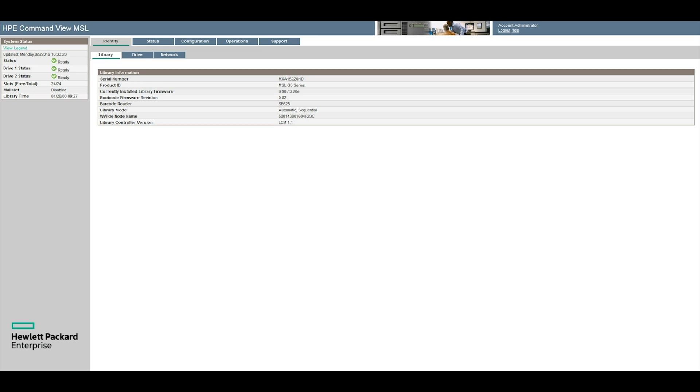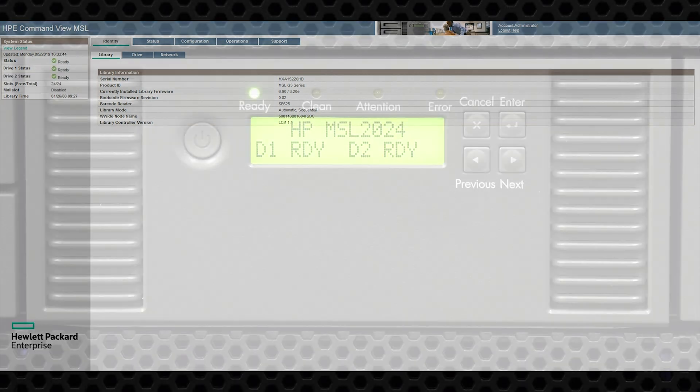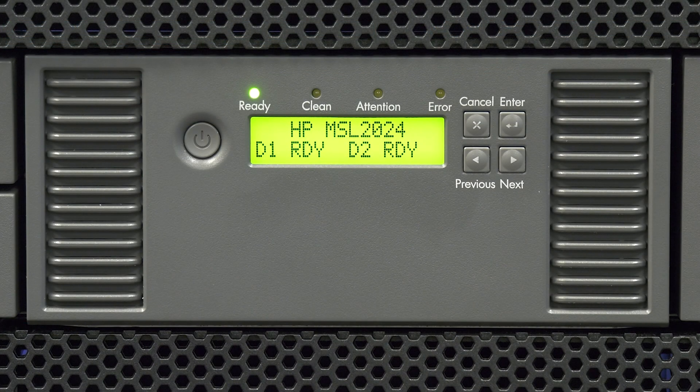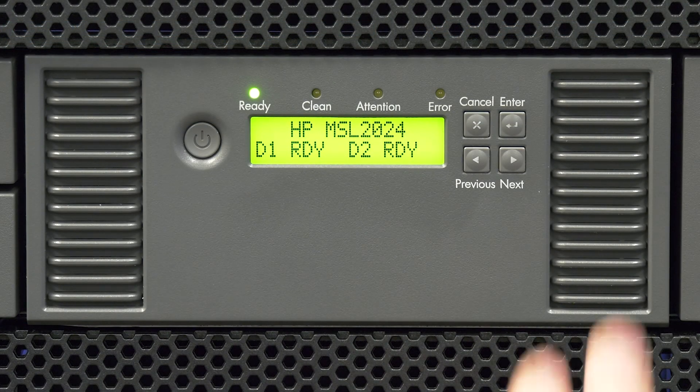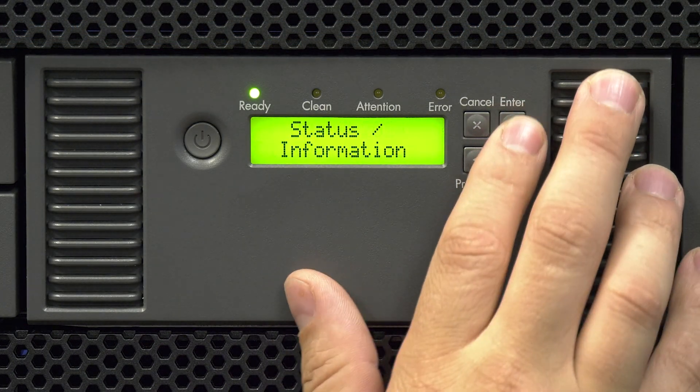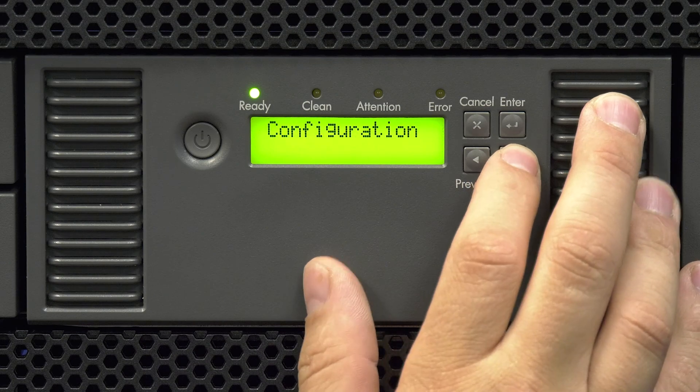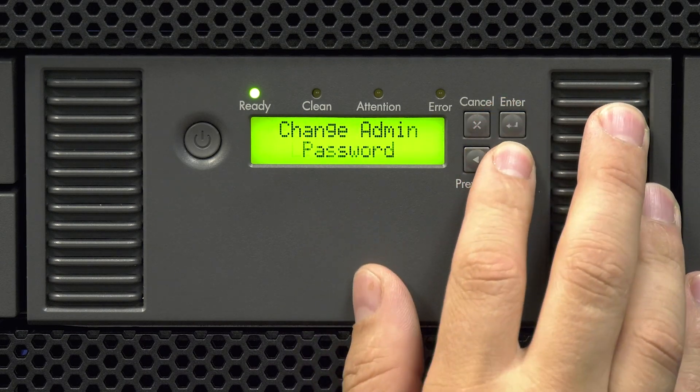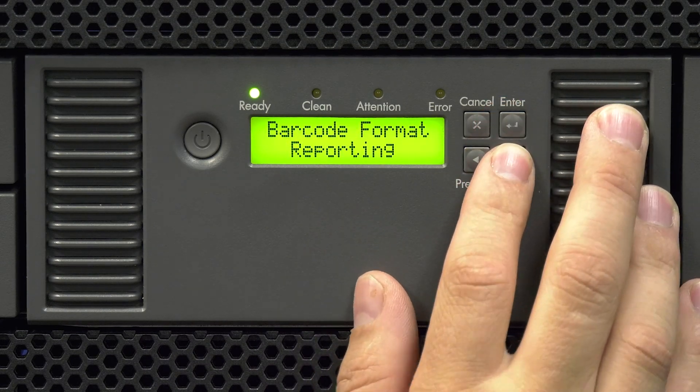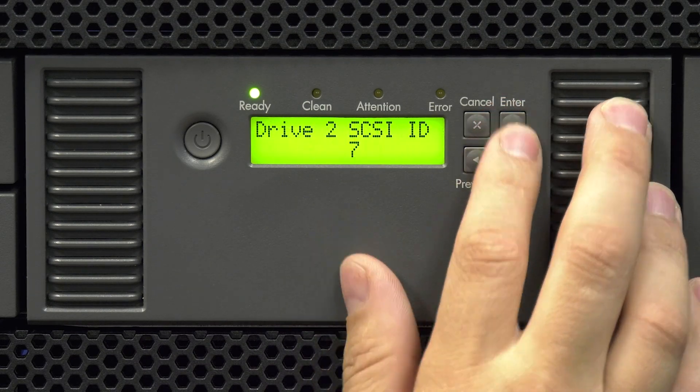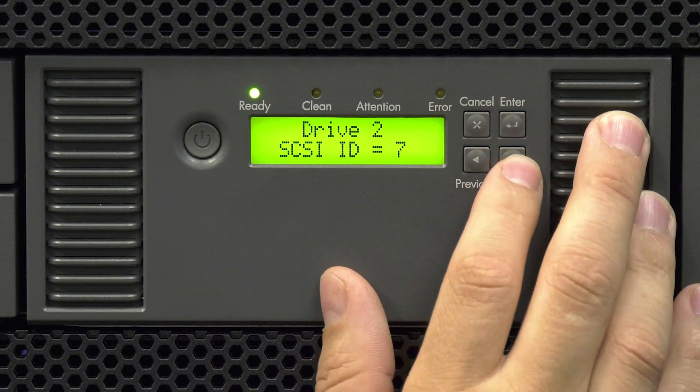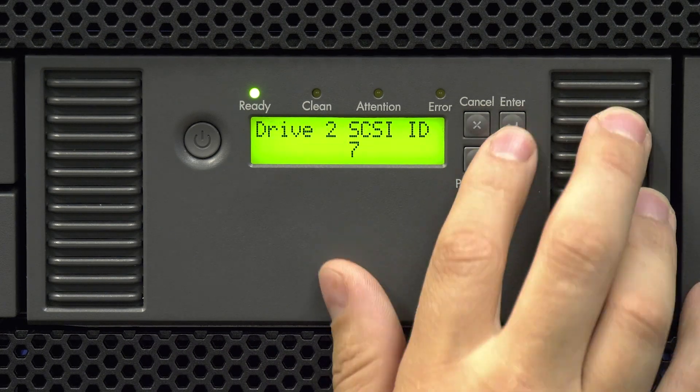If the drive you replaced has a SCSI data interface you will now need to set the SCSI ID to the same as the faulty drive had been. To do this from the front panel go to configuration and then scroll to change either drive 1 SCSI ID or drive 2 SCSI ID depending on which drive you replaced.